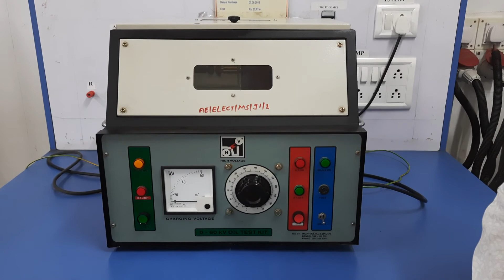Once we find the average breakdown voltage, we are able to calculate the dielectric strength of the oil insulating material using the formula: average breakdown voltage divided by the distance between the electrodes, which is fixed at 2.5 mm.